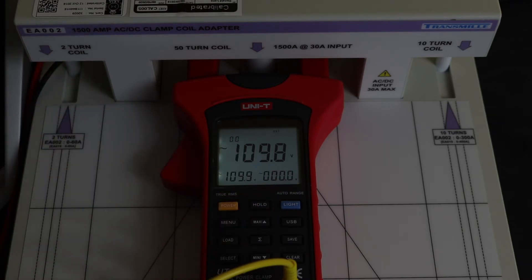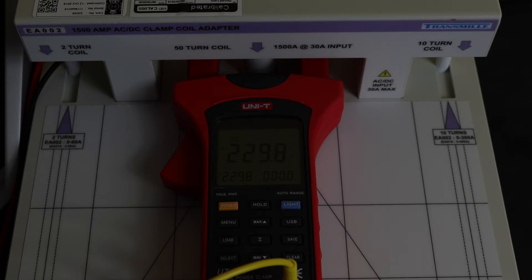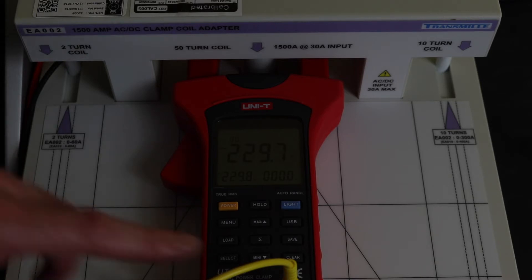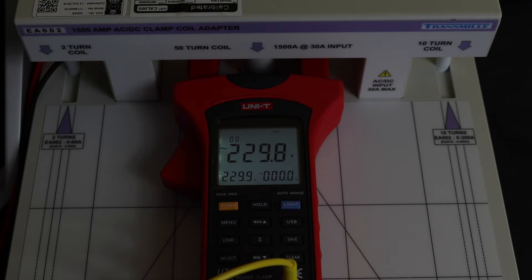230 between phases. Yeah, so that's 230 between phases, and then that one should be around about 400 - 398. So you can measure the three-phase like that.